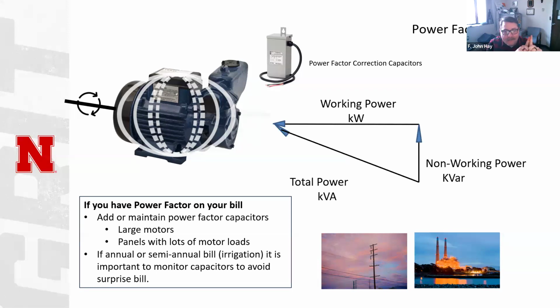I might pay $25 a horsepower or something—I don't know what the numbers are in different places, or $10 a horsepower or whatever—but I'm paying for that. Whereas if I didn't turn it on till the breakover, I'll call it May, all of a sudden I turn it on in May and I only get charged that power factor once during that billing period. So you can cause yourself some really high expense by turning things on and running them. You thought it was convenient, but it cost you a lot. So just double checking how that rate schedule charges and what those different billing periods are can really help avoid these silly charges that you didn't expect. I only call them silly because you only ran it for a little bit and thought you were doing something good, but it ended up not being as good, and it could have been avoidable.